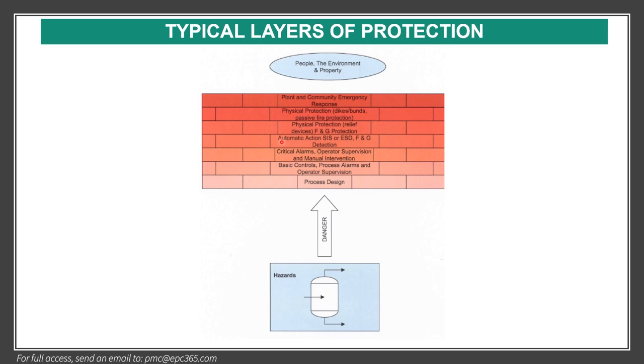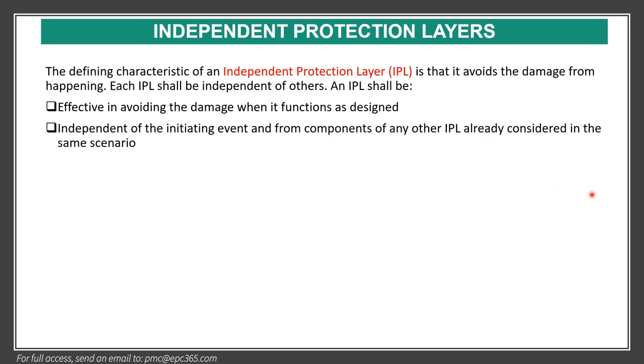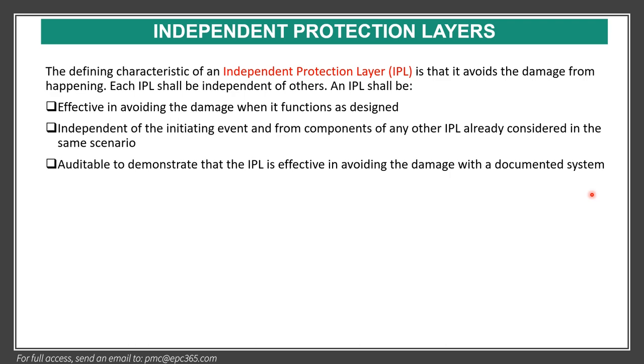If all these barriers fail, there is an effect on people, the environment, and property. We must understand the layers of protection. An independent protection layer, or IPL, must be effective in avoiding damage when functioning as designed. It should be independent of the initiating events and independent of components of any other IPL already considered in the same scenario. It should be auditable — able to demonstrate that the IPL is effective in avoiding damage with a documented system.